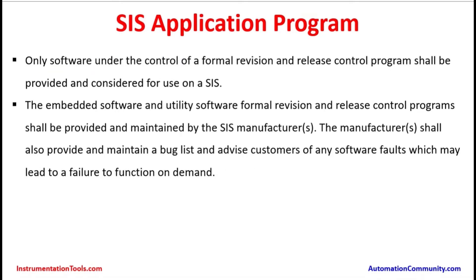Only software under the control of a formal revision and release control program shall be provided and considered for use on a SIS. The embedded software and utility software formal revision and release control programs shall be provided and maintained by the SIS manufacturers. The manufacturers shall also provide and maintain a bug list and advise customers of any software faults which may lead to a failure to function on demand.